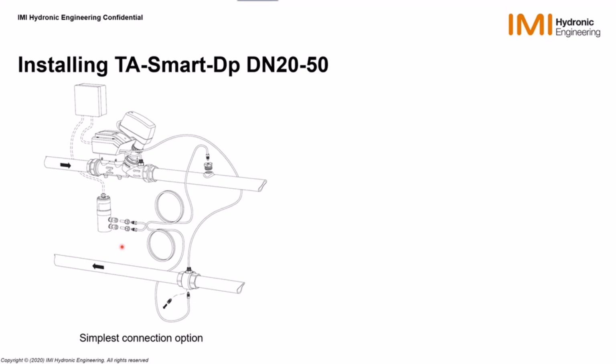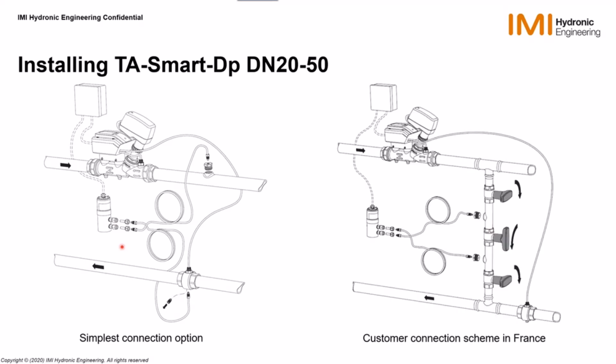But if you want to be safe, then you would need to implement something similar to this, which is what a number of installers have started to implement on the French market. This is a bypass with 3 ball valves. And basically what you do when you are installing the TSMart delta P sensor, you are simply opening this valve to make sure that you are bypassing between the two sides so that you get the same pressure applied on both. Before you do that, basically, you are isolating here and here from the network.